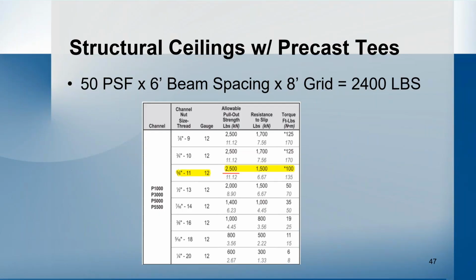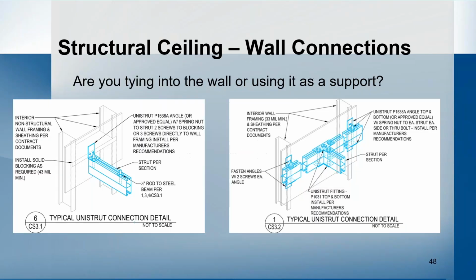As I mentioned with those channel nuts, in this case, if you had a 50 PSF load, your precast tees are spaced 6 foot on center and you have an 8 foot grid, you end up with a 2,400 pound reaction. So where the rod itself would be fine, typically with a 1/2 inch, because of the channel nut capacity, you need to go up to a 5/8 inch diameter in that case.